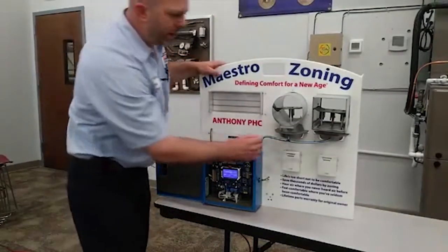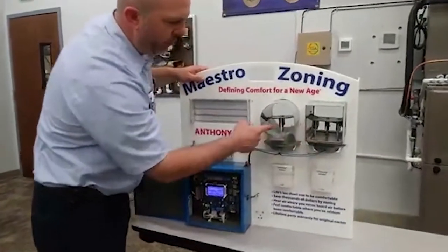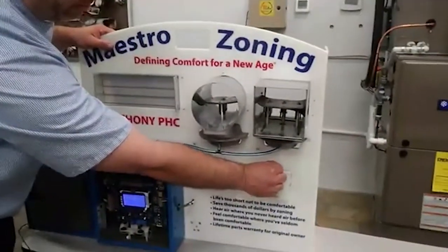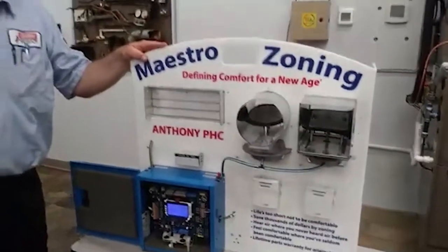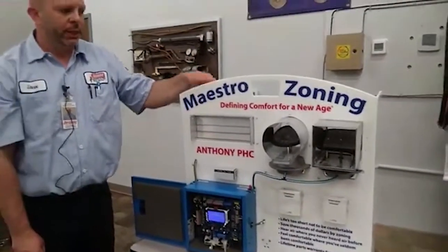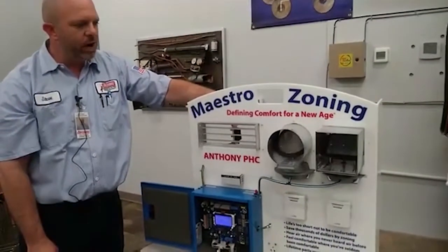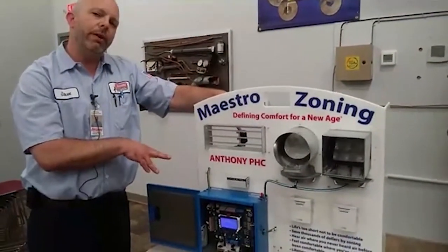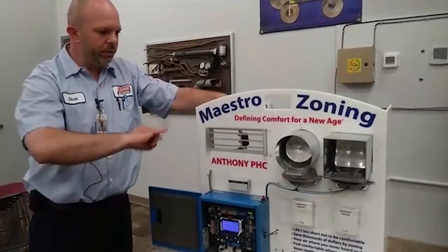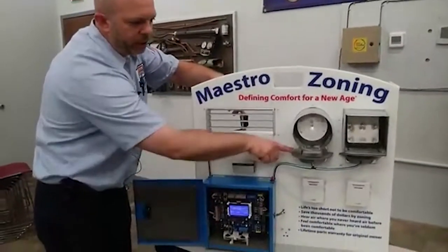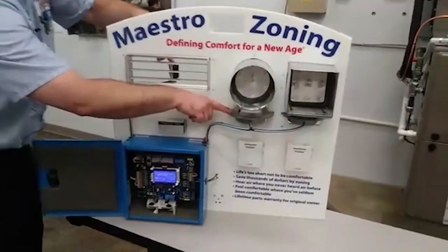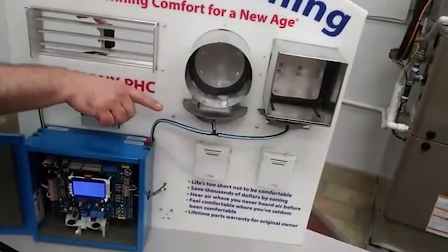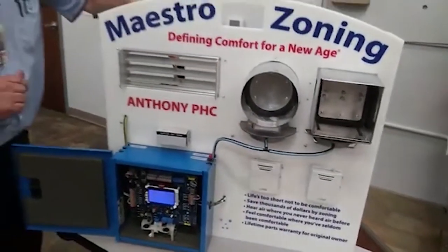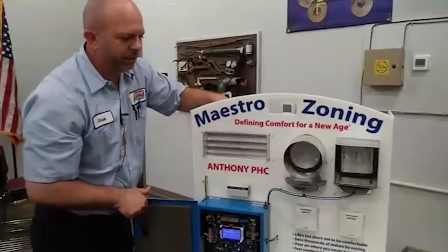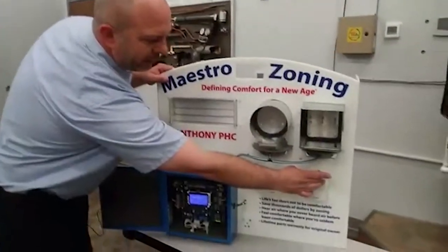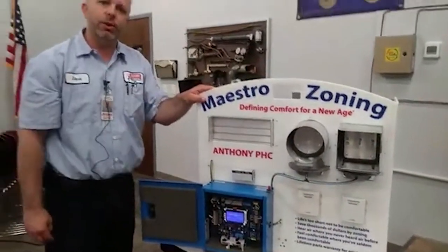Yes. So right now we have a call on this zone, so they're open. If I terminate my call, now my dampers are going to close. And if I have a call on this system here, now I'm going to force all my air to the other zone. So we can go either way. Now you'll see also on here I have my little yellow tab and it says open and closed. So if I have an unfinished basement, I can look up and tell if that particular damper is open or not. So we'll flip that back over and now you'll see them slowly start to open back up.